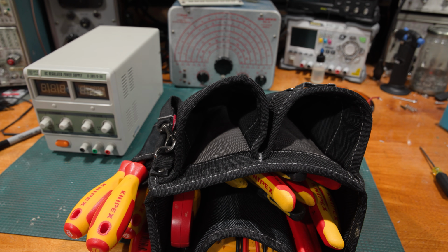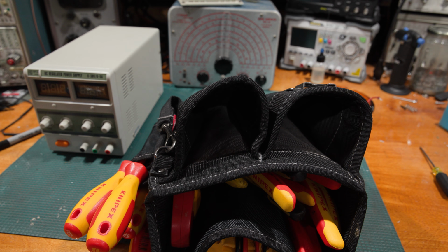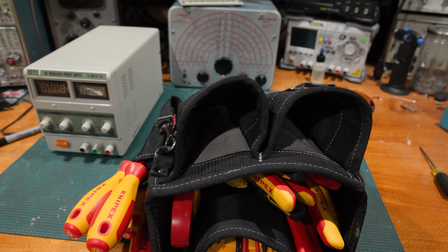I've also heard that especially with modern gear nowadays, with what's accessible, the calibration spec can really be tightened up on those units. So I'm looking forward to seeing how well we can get that done. The problem is those are AC units, and calibrating AC is a lot different and more complicated and a bigger pain in the butt than calibrating DC. But we always start with DC. Well, at least most calibration routines do.